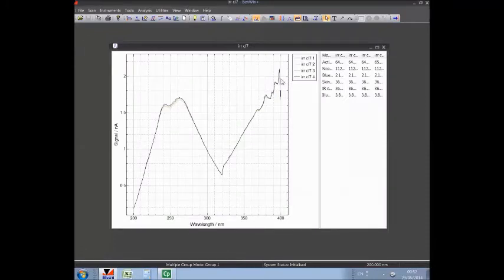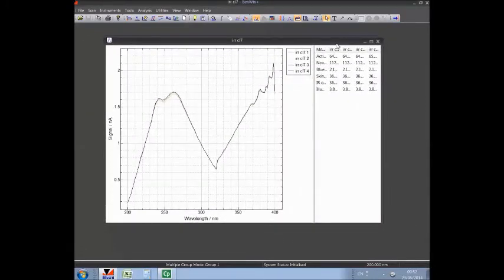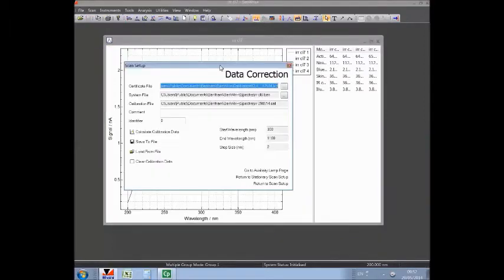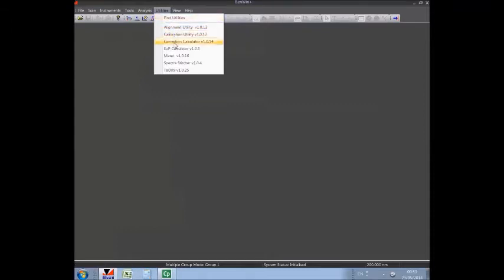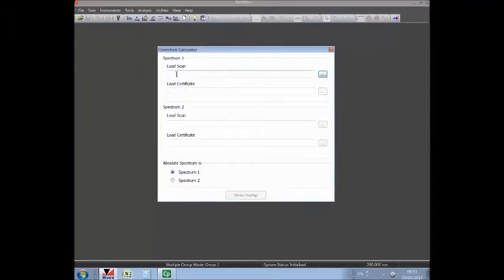Now, I don't take the average because we need to find a manner of generating, for both the CL6 and the CL7 calibrations, one continuous data correction file. In the scan data correction, we can see that only one lamp, one measurement of the lamp, can be accounted for. And it's for this reason that we have in utilities the correction calculator. So the correction calculator effectively generates the cal file, so the ratio of the certificate file of a lamp divided by the measurement of that lamp.